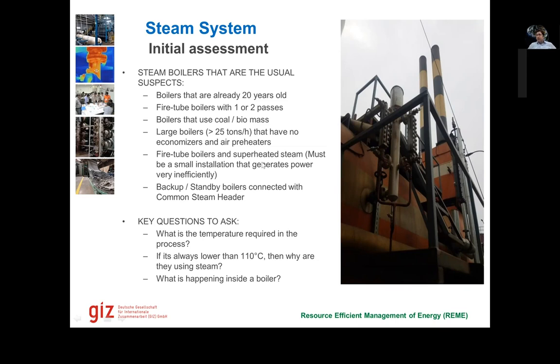These are critical points. Because they are connected to the common steam header, the main tank of these boilers also becomes a header because there's backflow of the steam. So a lot of condensation also takes place. Companies do not usually apply blow down to these boilers, but these also sometimes need blow down. Usually it is recommended that if there's a boiler which is on standby most of the time, install a solenoid valve that shuts its main line so that there's no back pressure going from the header to the boiler.